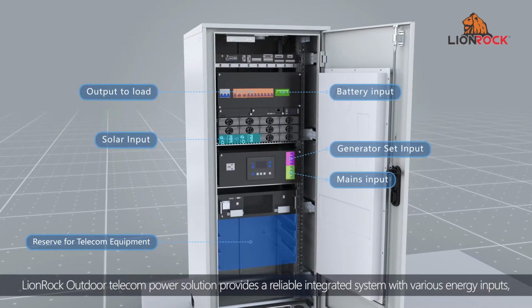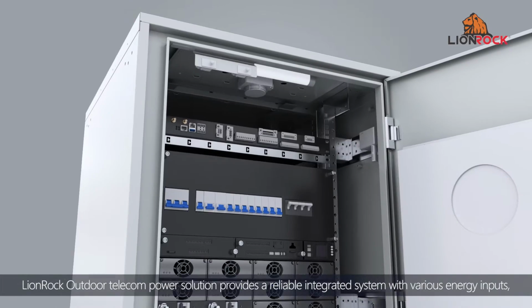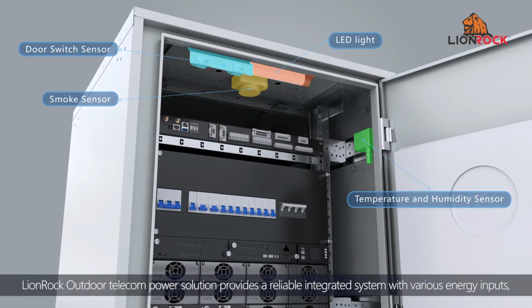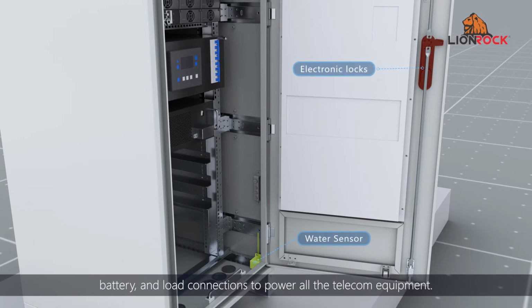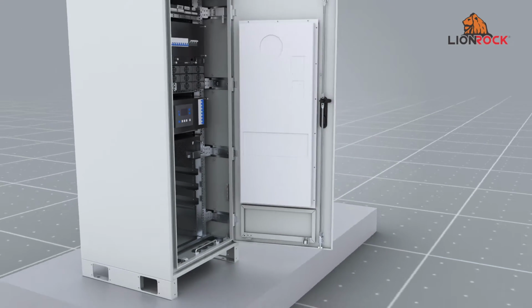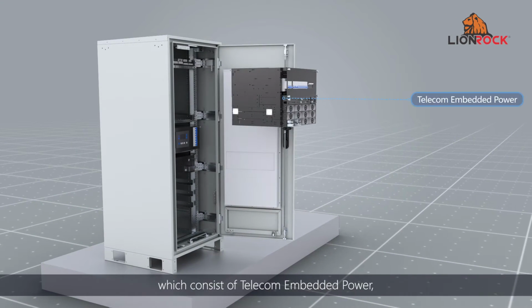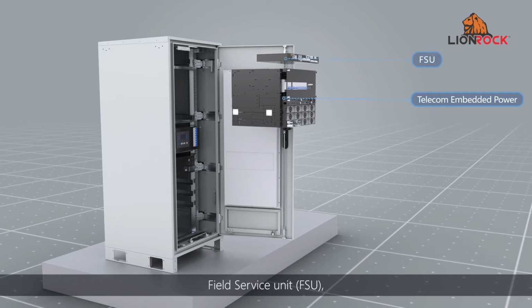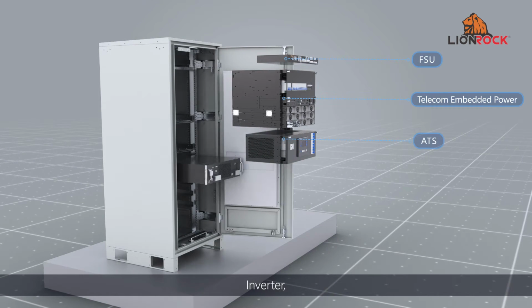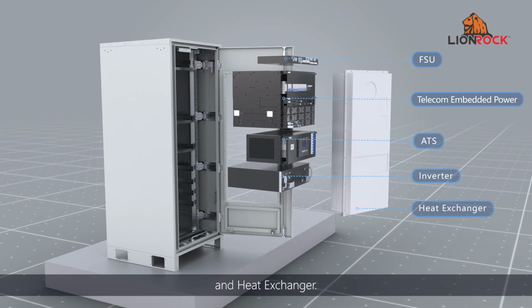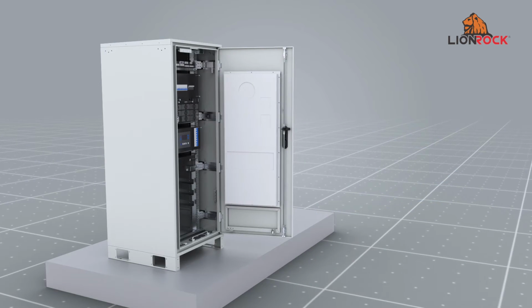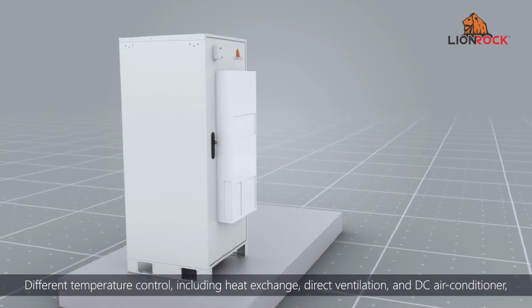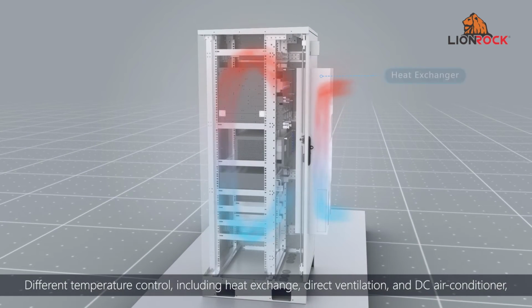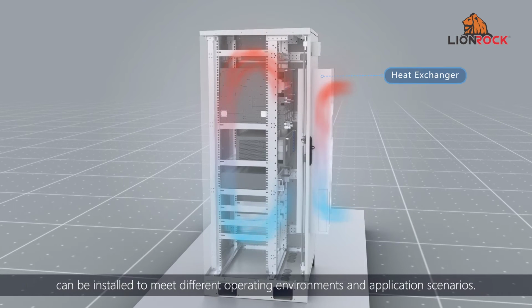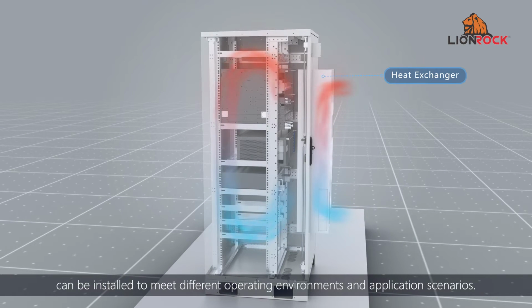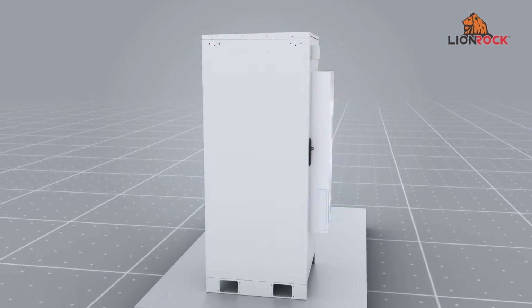LionRock Outdoor Telecom Power Solution provides a reliable integrated system with various energy inputs, battery, and load connections to power all the telecom equipment, which consists of telecom embedded power, field service unit, automatic transfer switch, inverter, and heat exchanger. Different temperature control, including heat exchange, direct ventilation, and DC air conditioner, can be installed to meet different operating environments and application scenarios.